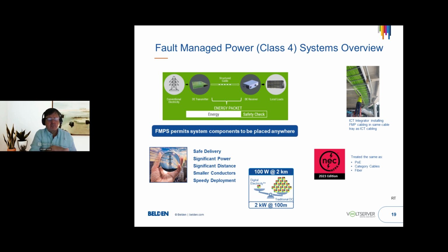In relation to the significant conductors and power argument, I have here on the bottom a graphic indicating the calculations I made to demonstrate how it's significantly fewer conductors to utilize this technology. Each one of the circles is a 4 conductor 18 gauge cable. With that 4 conductor 18 gauge cable, using digital electricity, a single one can deliver 100 watts to 2 kilometers. Likewise, with that same cable, I could also deliver 2 kilowatts, but a much shorter distance, at 100 meters. So keep that ratio in mind.